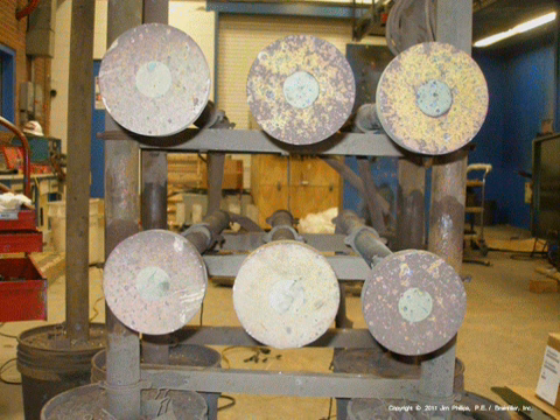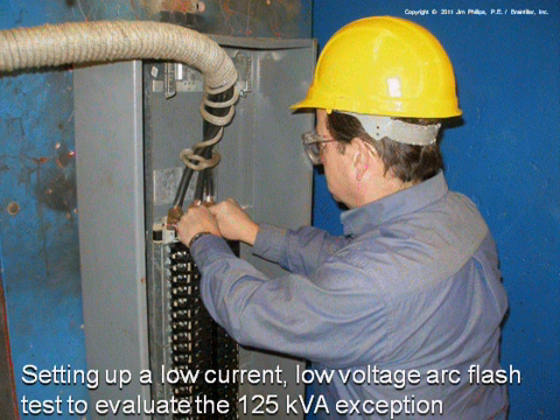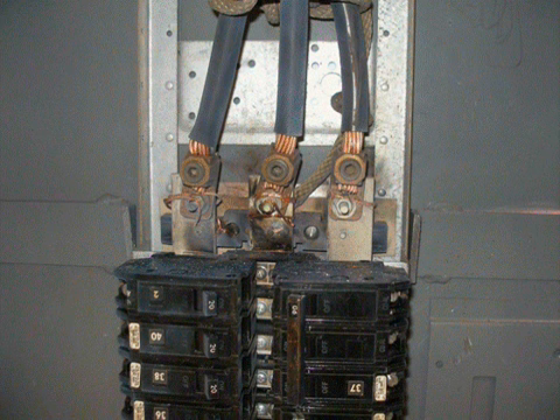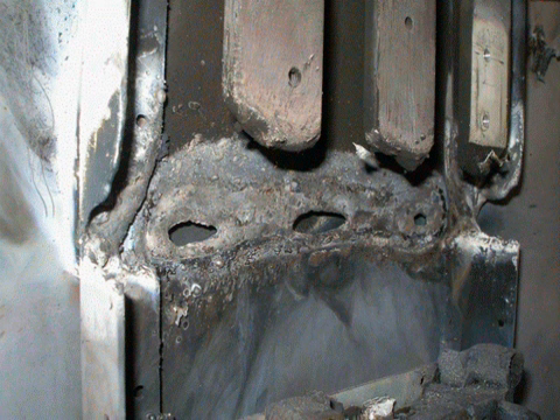This is from some testing that I was involved in last year. We were taking a look at low voltage, low current arc flash using actual equipment. You look at the result up here on the line side, and it looks like the trigger wire melted and not much else. But then you go down to the load side, and we lost quite a bit of bus. So when you think you're safe, sometimes the information points you in a direction that you hadn't planned.